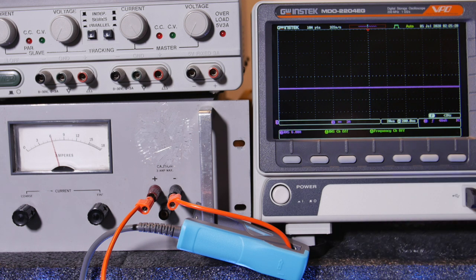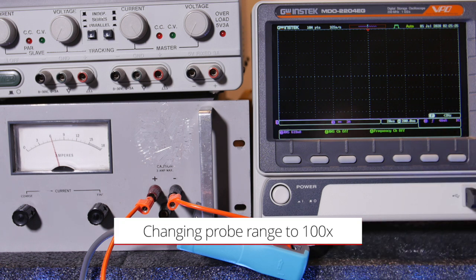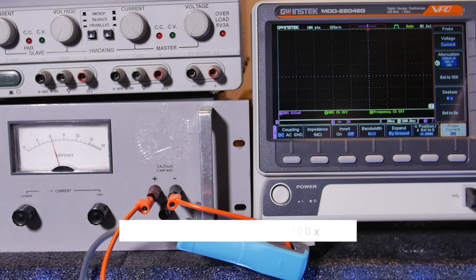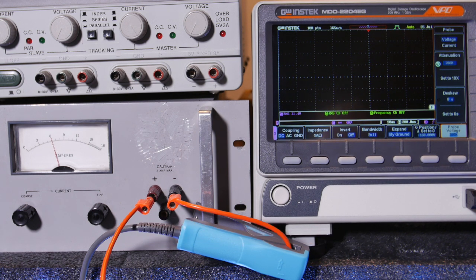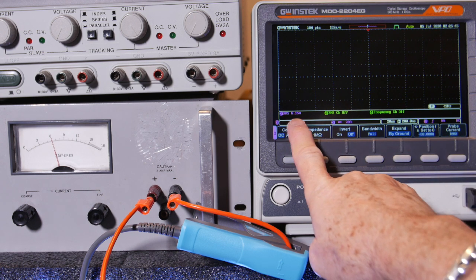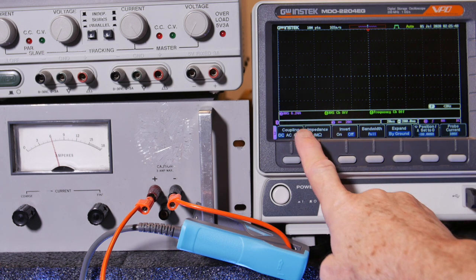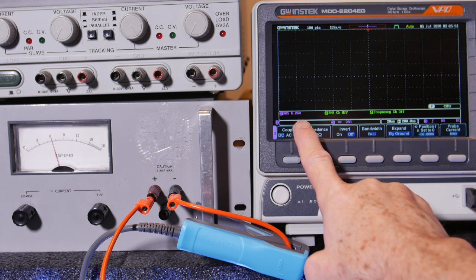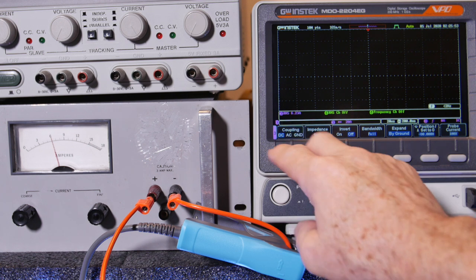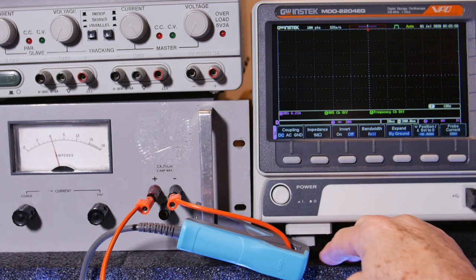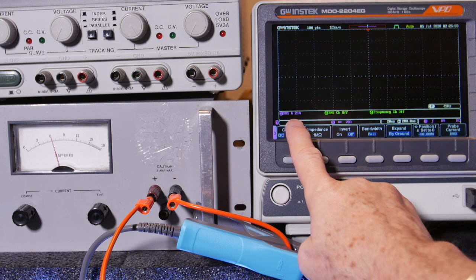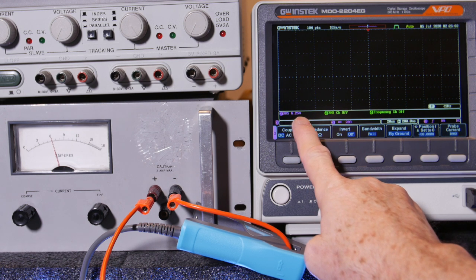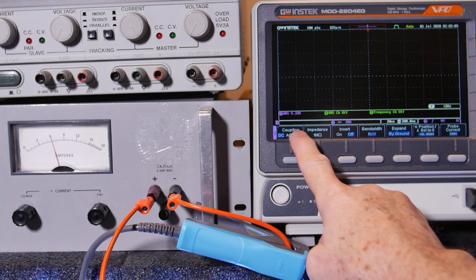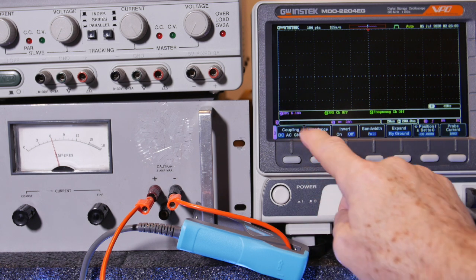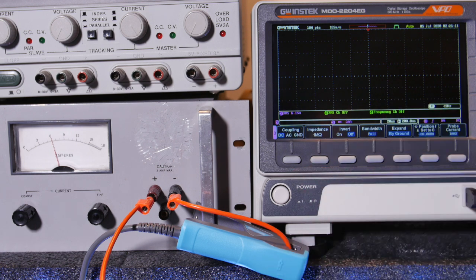Now I'm going to go ahead and change the probe for 100 amps per division. And then go to the scope and go to times 100. Okay. Alright, and it's 6.14, something like that. So it's giving a slightly higher reading at the 100 amp scale, showing the resolution compared to the 10 amp scale. That's pretty darn good because that is 6.2 maybe. It's kind of bouncing around. That's pretty darn good, I think, for a 100 amp scale to be that accurate down at 6 amps.